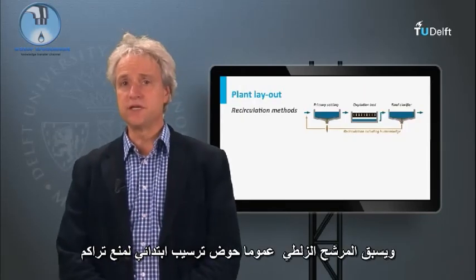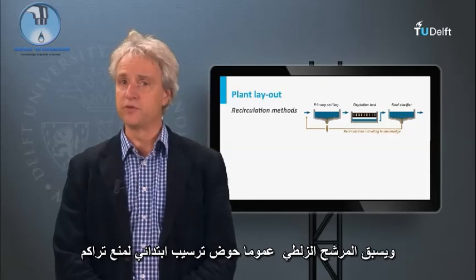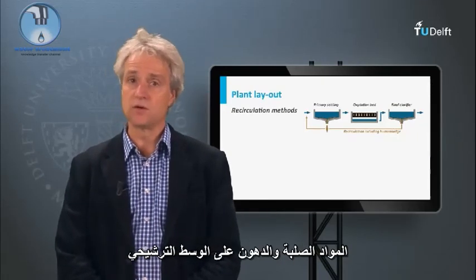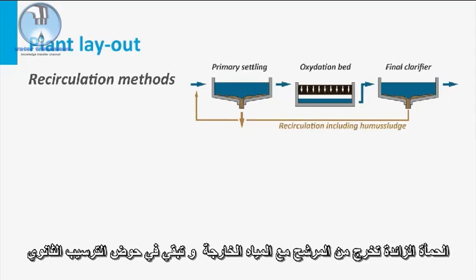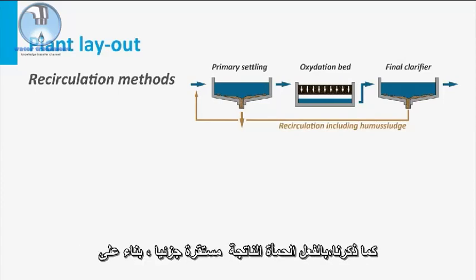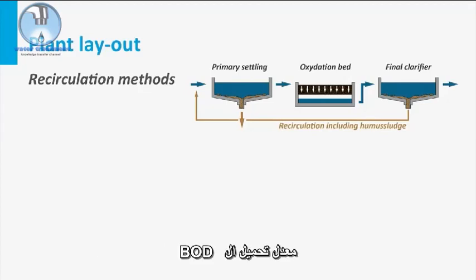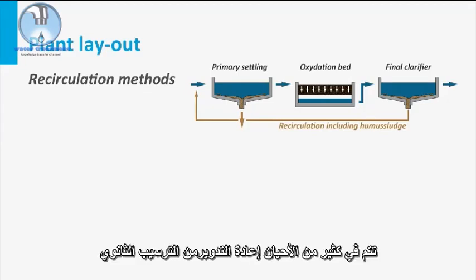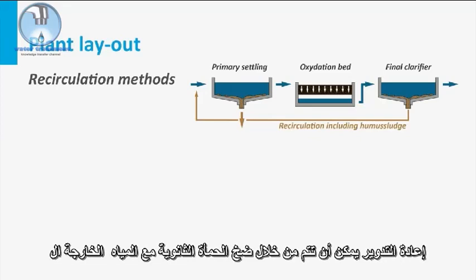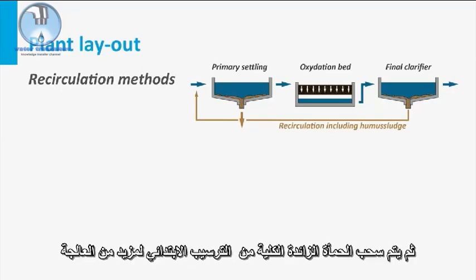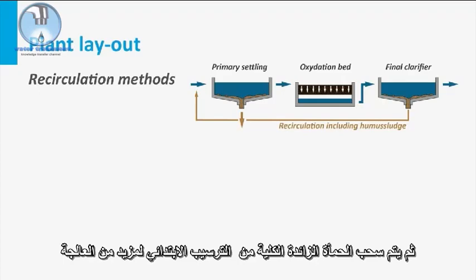A trickling filter is generally preceded by a primary clarifier to prevent the accumulation of solids and fats onto the filter bed. Excess sludge leaves the filter with the effluent and is retained in a secondary clarifier. As mentioned, the produced sludge is already partly stabilized, dependent on the applied BOD loading rate. From the secondary clarifier, often recycling is performed. Recycling can be performed by pumping the secondary sludge with the nitrified effluent to the primary clarifier. The overall excess sludge is then withdrawn from the primary clarifier for further treatment.